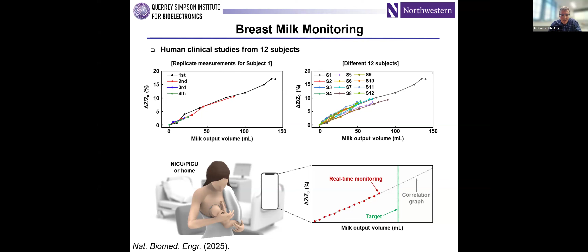Then we were curious, is there a universal calibration factor? And we did 12 different participants in these studies. And you can see that there's a rough correspondence, but there are anatomical variations associated with breast size and body type and so on. And so to get the highest accuracy, you do a calibration on a per individual basis. And so this provides a solution to an unmet clinical need that turns out to be important for new mothers. So that's one example of measuring flow using skin-interfaced wireless devices.